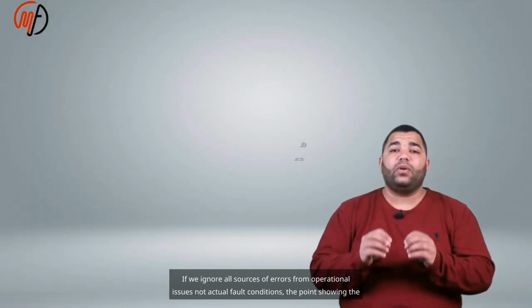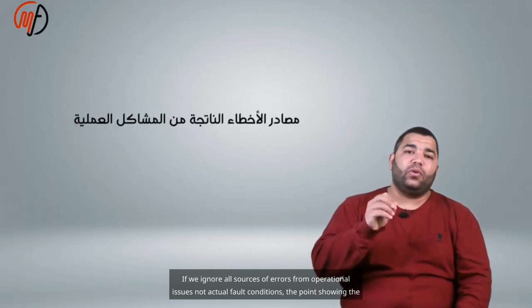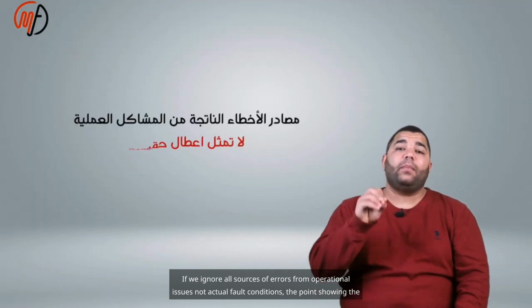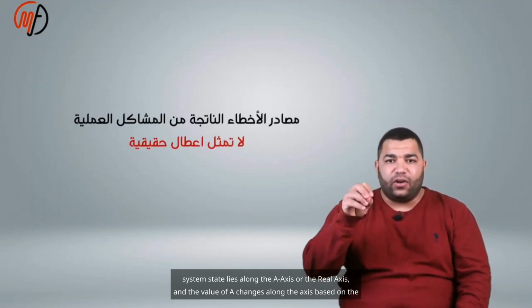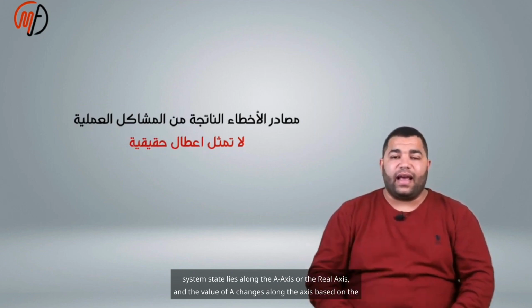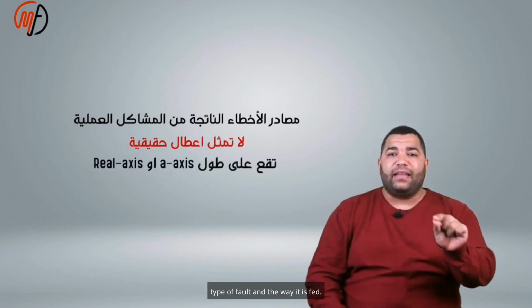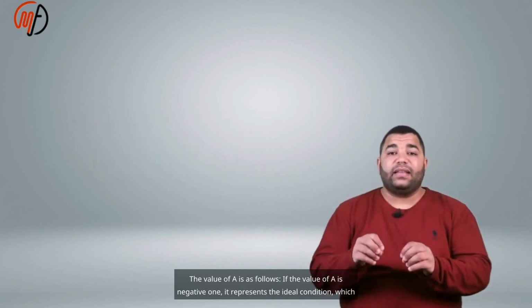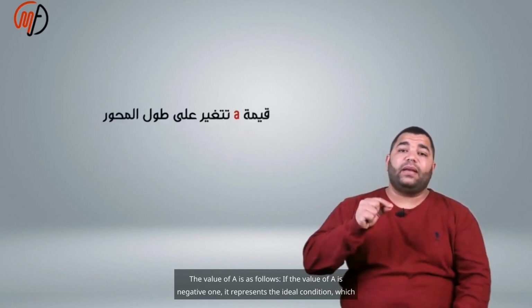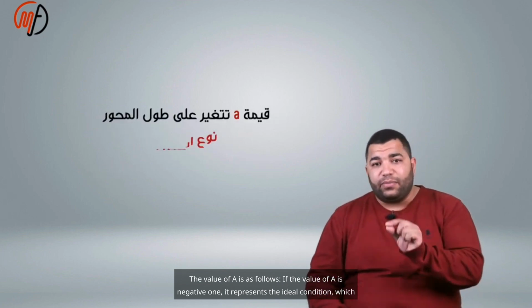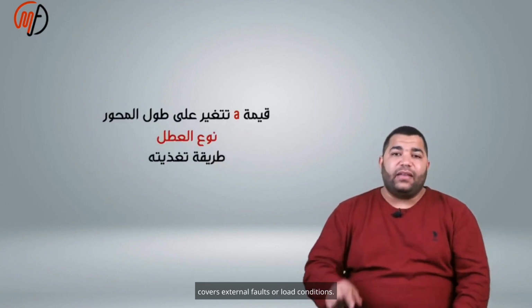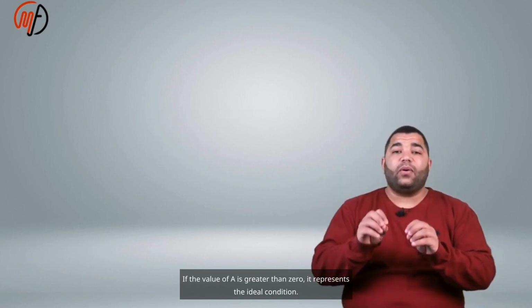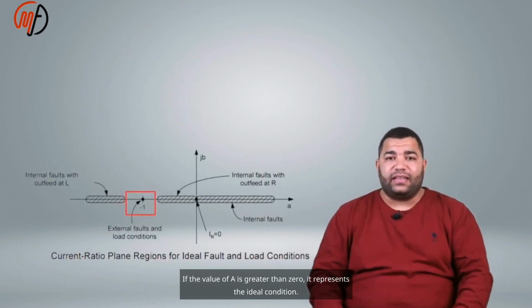If we ignore all sources of errors from operational issues, not actual fault conditions, the point showing the system state lies along the A-axis or the real axis, and the value of A changes along the axis based on the type of fault and the way it is fed. The value of A is as follows. If the value of A is -1, it represents the ideal condition, which covers external faults or load conditions.